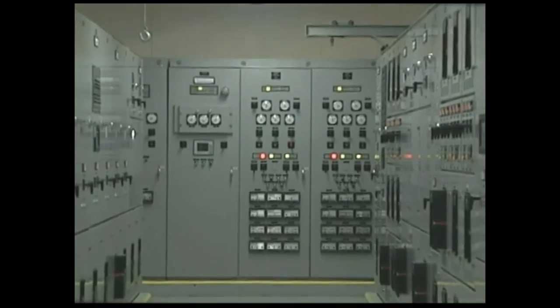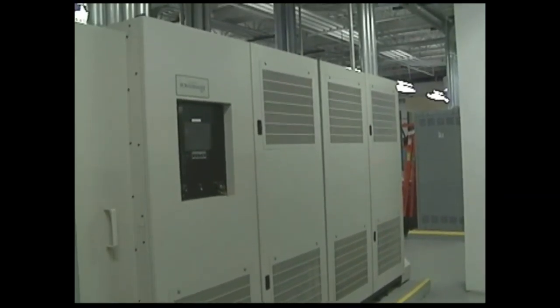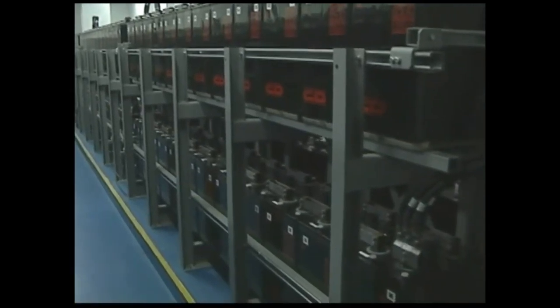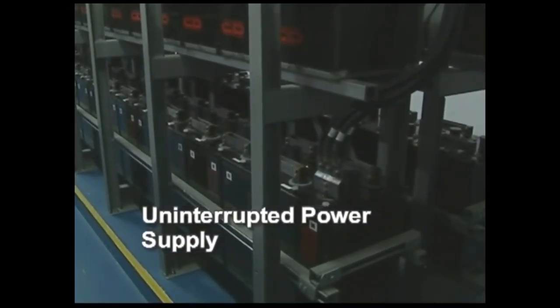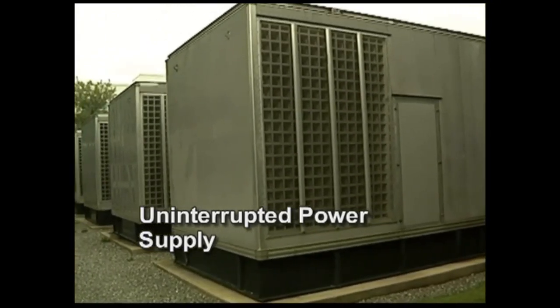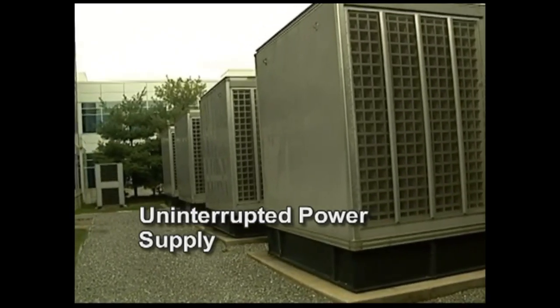Today, we have built a supportive environment with unparalleled power, network, and cooling. The entire electrical system has built-in redundancy to guarantee continuous operation. The parallel UPS systems with battery backup are redundantly supplied by diversely distributed utility power and backed up by three generators, each of which are sized to run the entire site at full load for 24 hours minimum, with hot refuel capability.